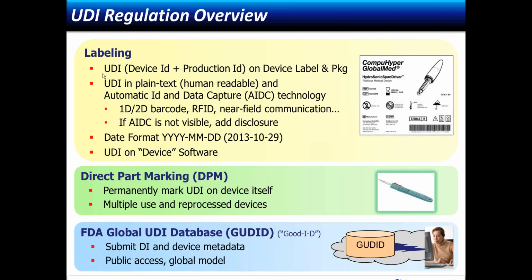So as far as labeling is concerned, there's a unique device identifier that is identified in the final rule, and it's a composite of two separate identifiers. One is a device ID, and that is static, referring to the labeler itself and a particular model and version. And then there's a second portion, the production ID. The production ID will capture information that is much more dynamic. It's information about a particular serial number, the lot number, might be an expiration date, manufacturing date, and so on. But that production ID, along with the device ID, needs to appear on the label and also on the package.